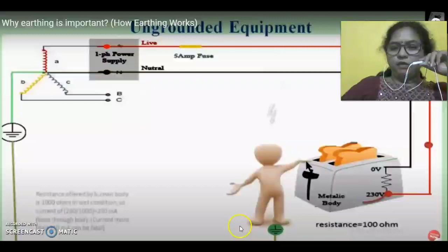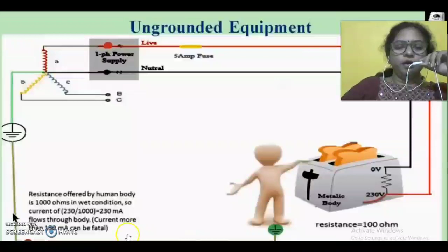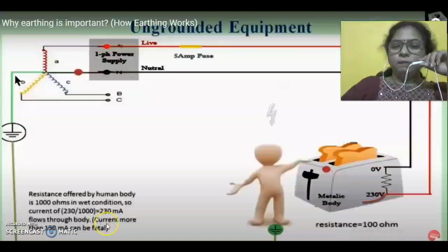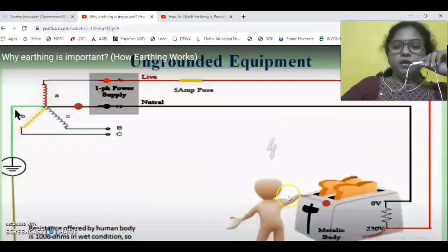So we will see that this metal is not grounded, and so if a person comes in contact with this toaster, then the person is in contact with ground, and this earth fault current will flow through this human body. Now this fault current will be equal to 230 divided by human resistance. Suppose it is 1000 ohm, then 230 milliampere current will flow through this body. Now this 230 milliampere may be harmful for the person, but the equipment is not protected.